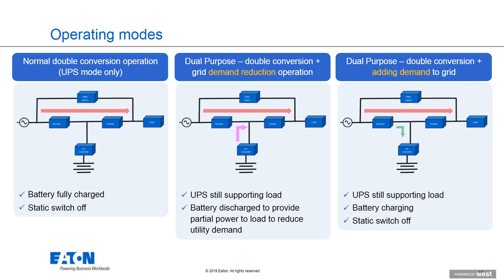As a result, we're able to reduce demand from the incoming power source. Now, what about the other side of the coin, on the far right, where we're operating in double conversion and adding demand to the grid? Why would we want to do that?